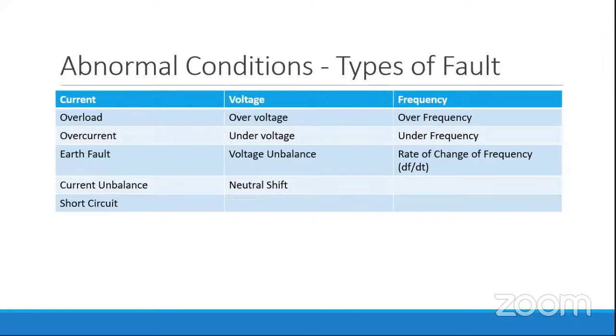In terms of voltage, there are certain faults, like over voltage, under voltage, voltage unbalance, and neutral shift. In terms of frequency, it will be over frequency, under frequency, and rate of change of frequency. That usually occurs from the grid end, and when there is in-house generation or a generator, this protection comes into the picture: rate of change of frequency, over frequency, and under frequency.